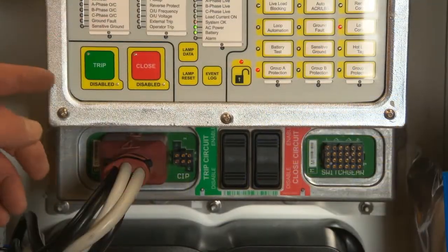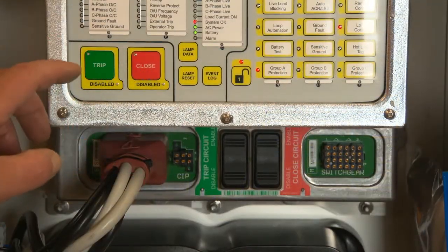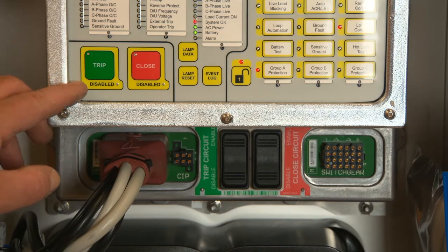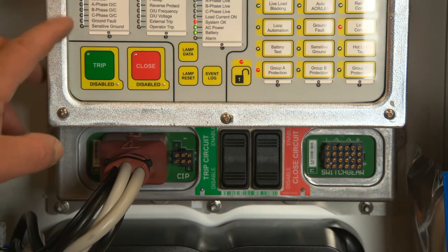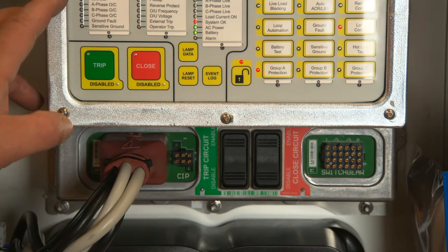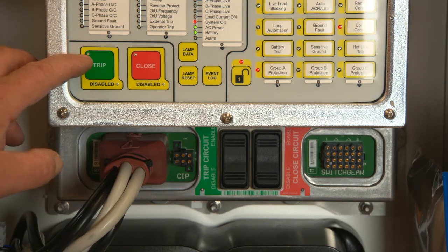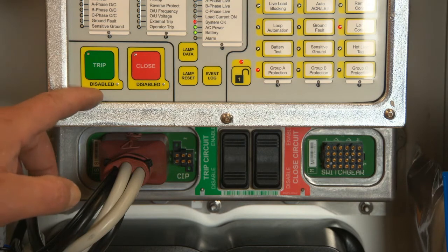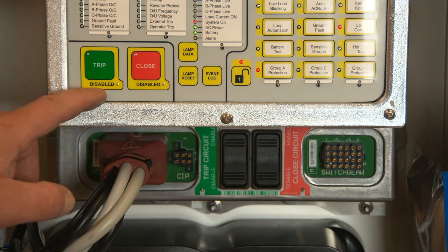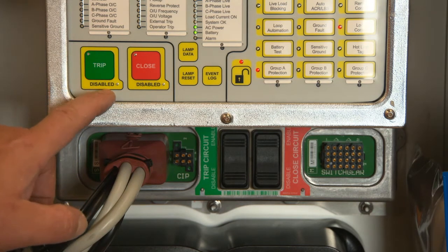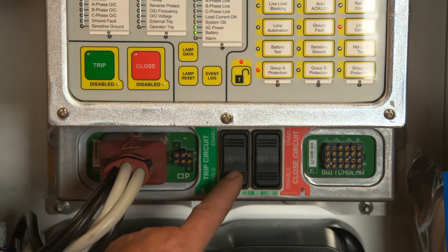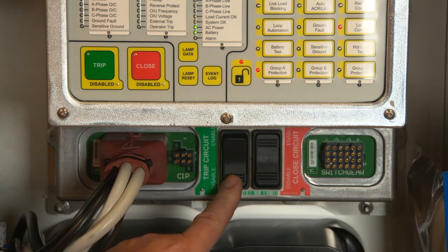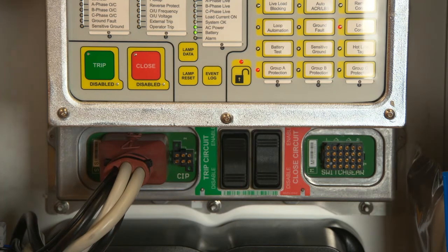Trip and close. If this recloser were tripped open, there would be a lockout indication above. The LED here on the trip button will also illuminate. The trip disabled indicator will illuminate after pressing the Disable Trip Circuit button below. To reactivate, press the Enable Trip Circuit button. The disabled indicator will now turn off. You may now trip the unit.